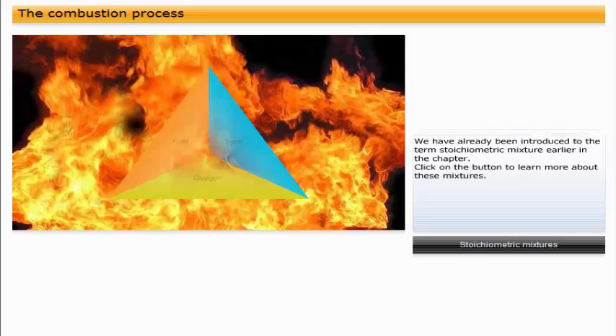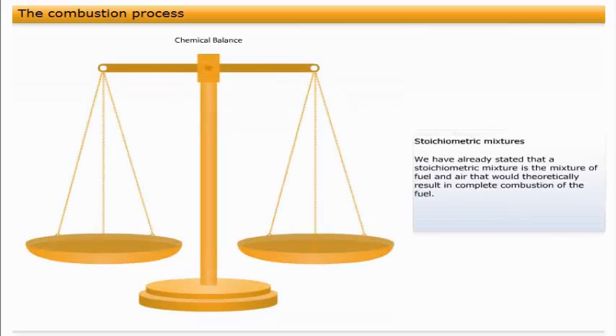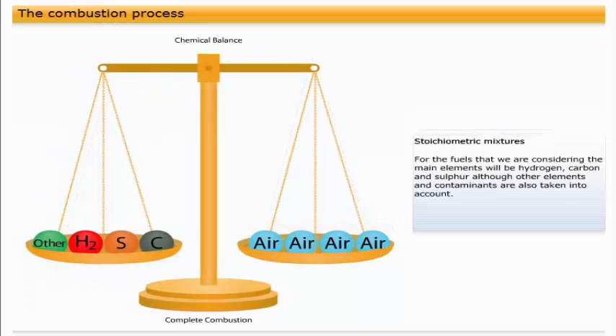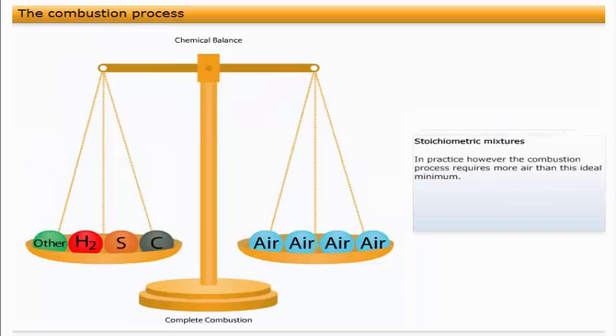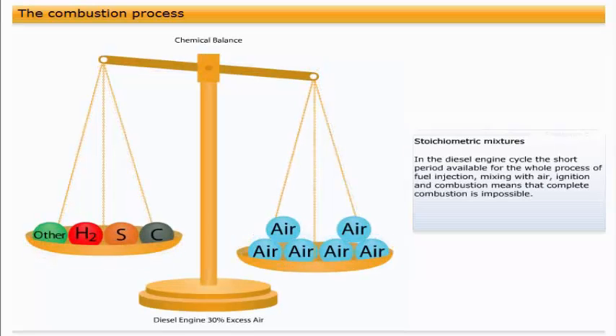We have already been introduced to the term stoichiometric mixture earlier in the chapter. A stoichiometric mixture is the mixture of fuel and air that would theoretically result in complete combustion of the fuel. The amount can be calculated by considering exactly how much air is required for the complete combustion of each of the elements within the fuel. For the fuels that we are considering, the main elements will be hydrogen, carbon, and sulfur, although other elements and contaminants are also taken into account. In practice, however, the combustion process requires more air than this ideal minimum.